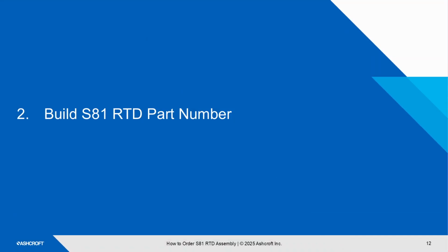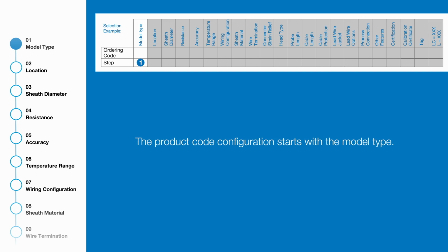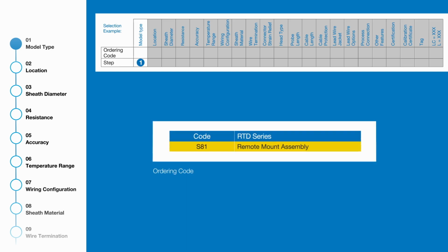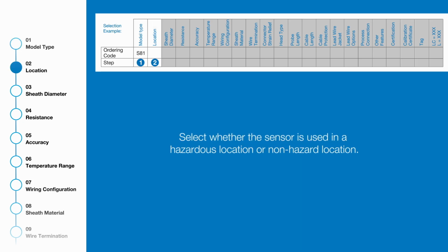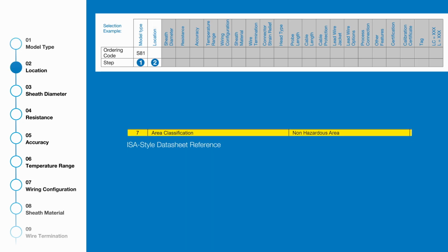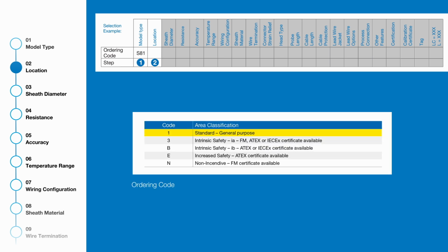Great, Dave. Once you have the thermowell part number, now it's time to build the RTD and transmitter part numbers, correct? That's right. The RTD part number will be the second part number that is needed. There are 22 steps. Let's go through each one now. The part number starts with the model type, which is S81. For the location, the area classification was non-hazardous, so we're going to select 1, standard general purpose.